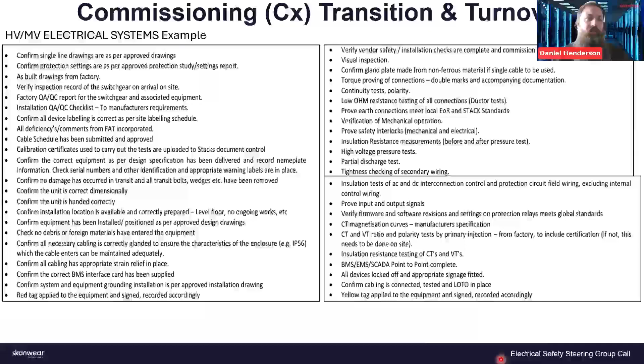Something that Wayne's put in here is just some examples, and they're quite thorough. This is based around switchgear essentially in the first instance. He'll be putting it into a tidy document once we agree on the format, but this is the level 2 side of things, where it's gone from the factory acceptance test, which should have already been completed in level 1 - again, I think he's got a draft template of that.